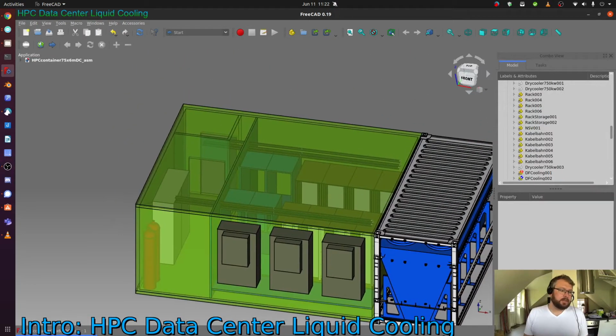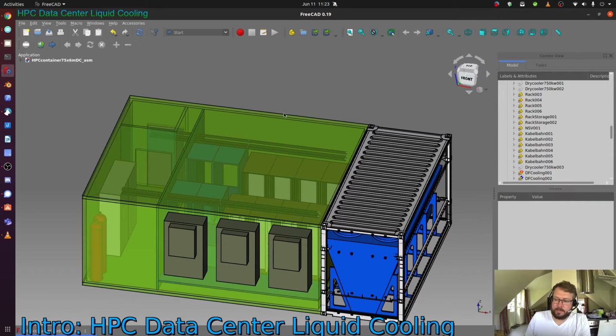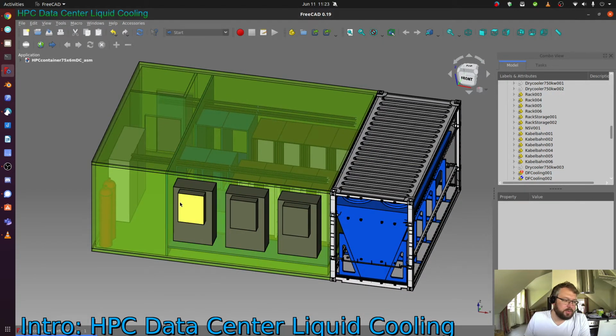This is displayed here with the empty racks. These usually would be full, but these are air-cooled storage and admin racks. Most of the storage components we looked into are still air-cooled. And the air cooling we achieve with these direct free cooling units; at maximum capacity we would need 3 of those. They enable all residual heat that is not captured by the direct-to-chip water cooling systems to be handled, so that the whole white space can be temperature stable using direct free cooling equipment.